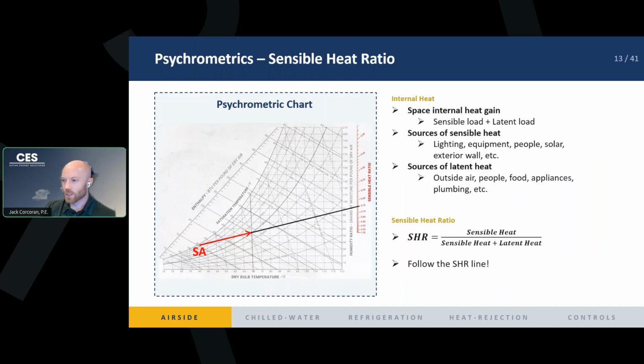So if you add up all your BTUs of sensible and all your BTUs of latent, you can use the equation at the bottom and you can figure out what your sensible heat ratio is. Basically, it's 1 if you have no moisture in the space, and it's closer to 0 if you have no sensible. It's all latent load.